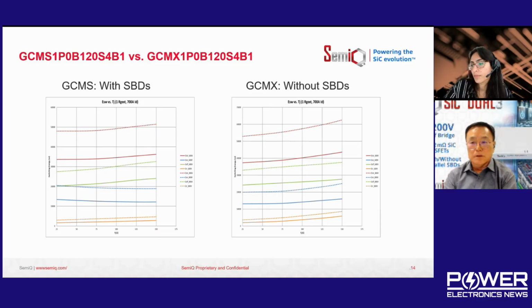But AI data centers significantly change the power conversion efficiency requirement, because an industrial drive usually runs about 8 to 10 hours per day, but an AI data center runs at full power 24 hours, 365 days. So conversion efficiency is so important, and we try to maximize it for those applications: the highest conversion efficiency and the lowest heat dissipation requirement. By adding the silicon carbide parallel diode inside the module, the overall switching loss is reduced, mainly because of reverse recovery charge reduction. Also, the Schottky barrier diode has only a constant or fixed junction capacitance.